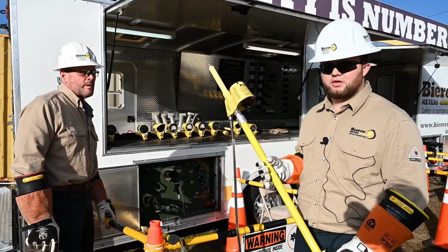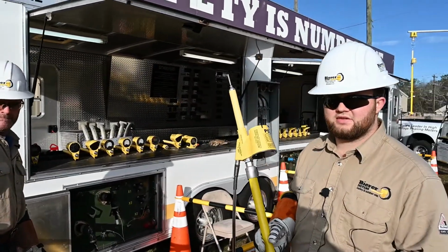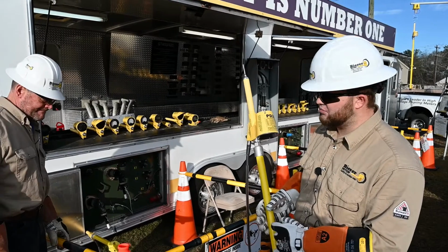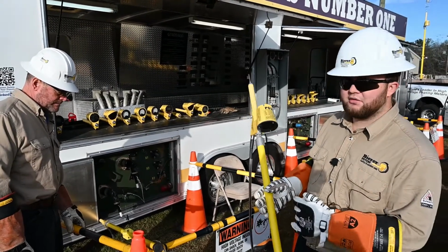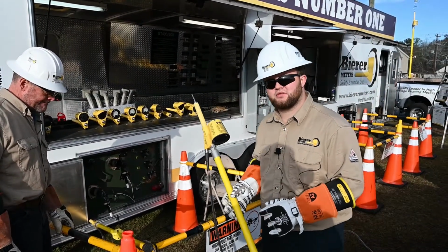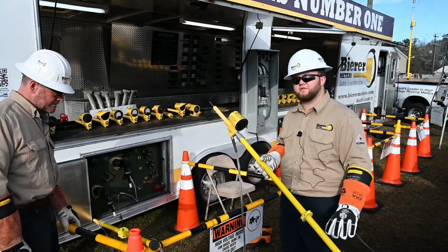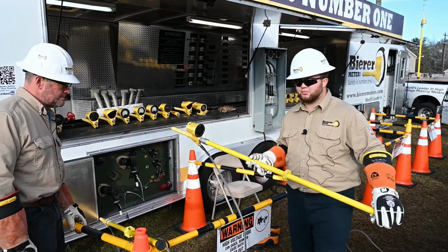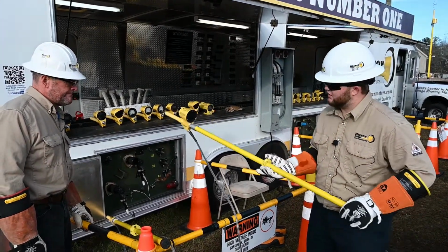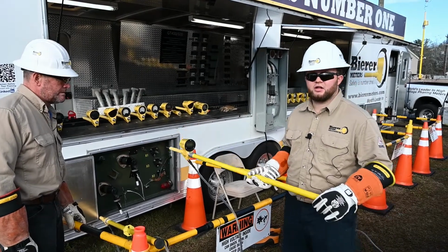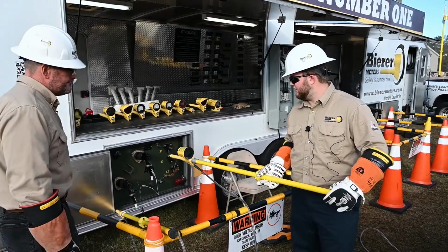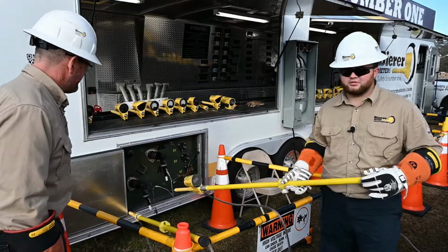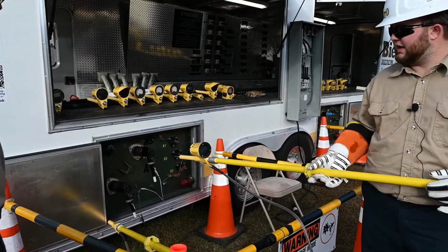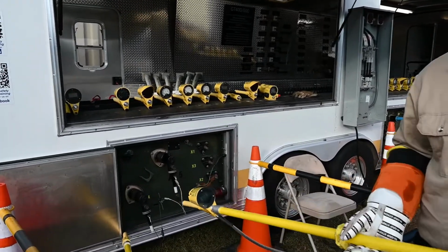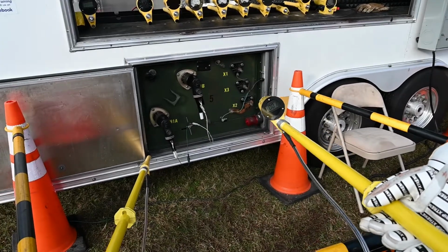When using a corded tool, if you can use it to phase or take voltage off a test point, we highly recommend doing so because the potential there is obviously less, so it's a safer practice. But it's a little different from just phasing on a straight conductor. Since each of these elbows cures differently, each capacitive test point is going to have a slightly different resistance value.